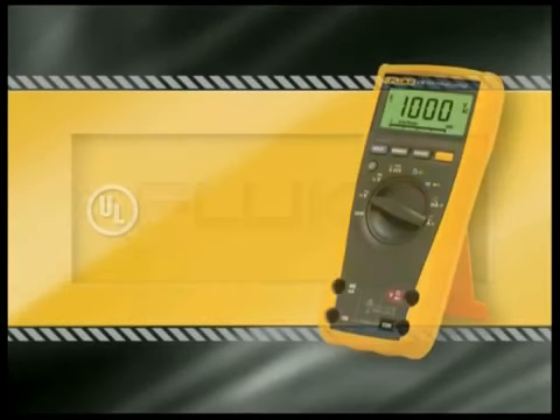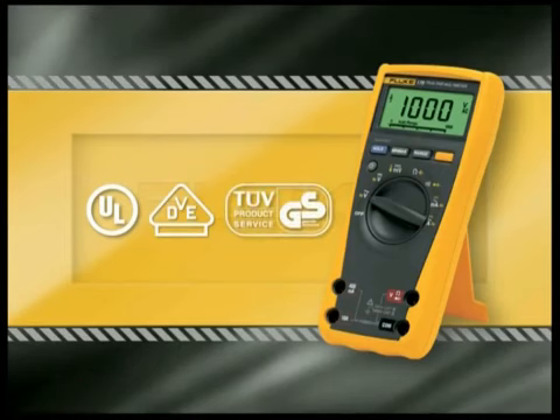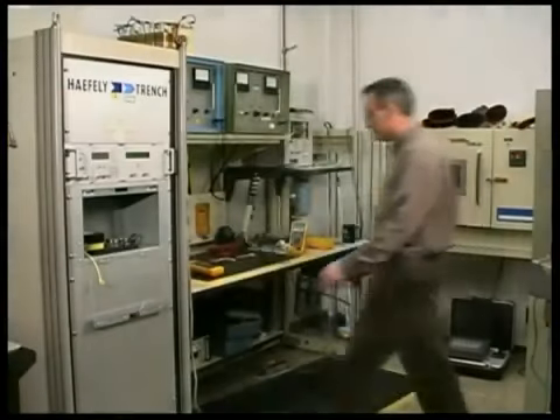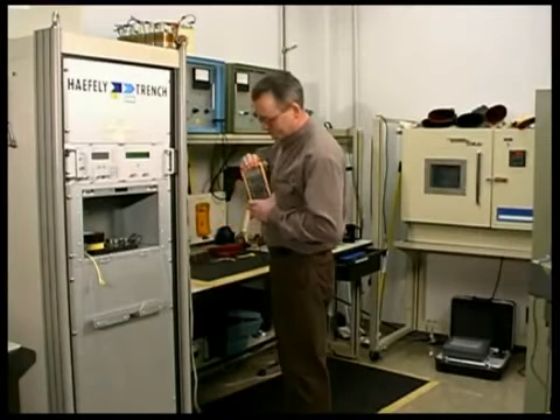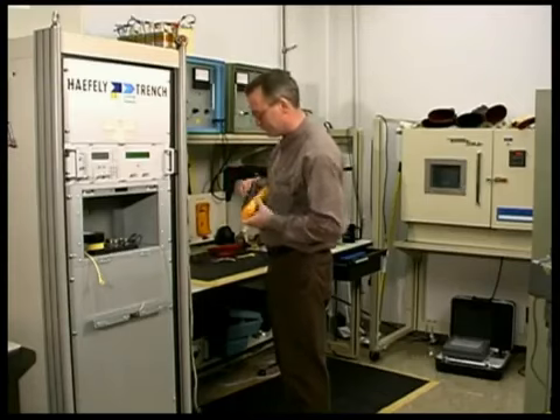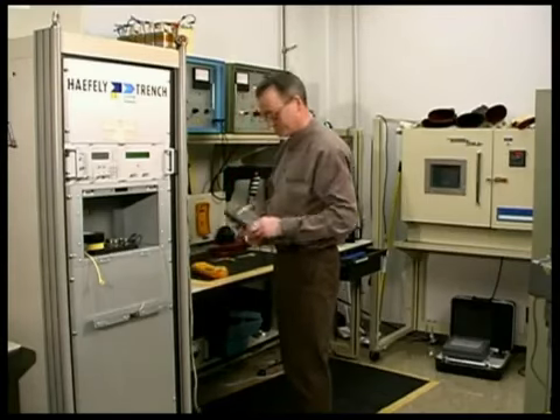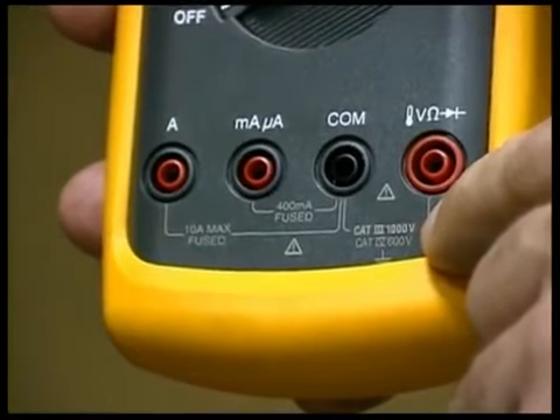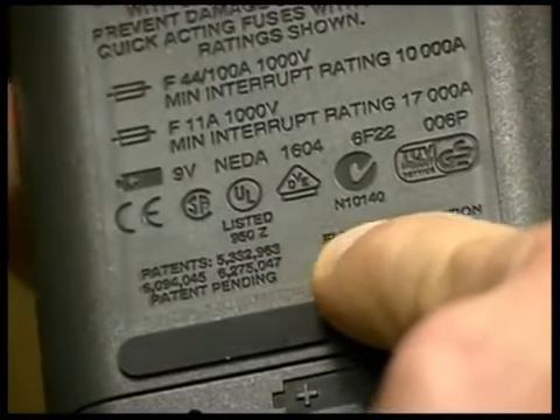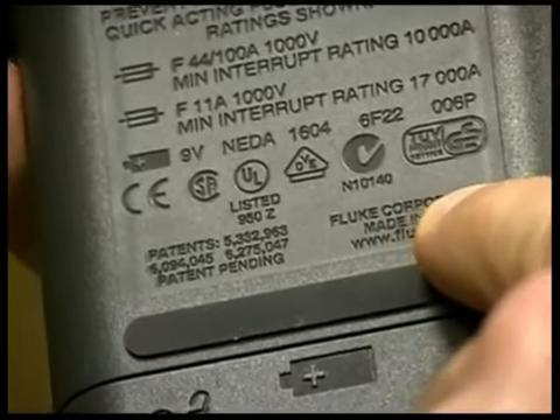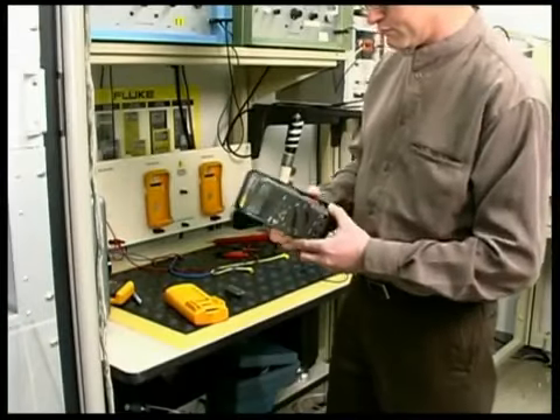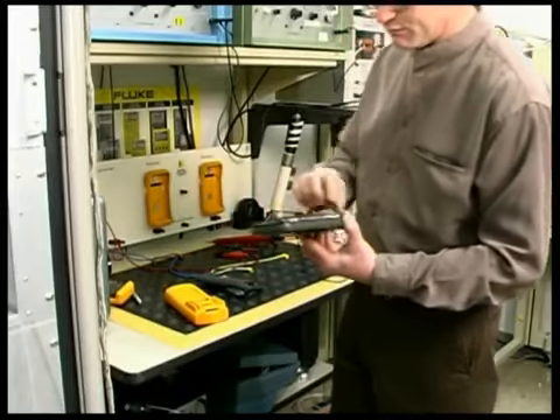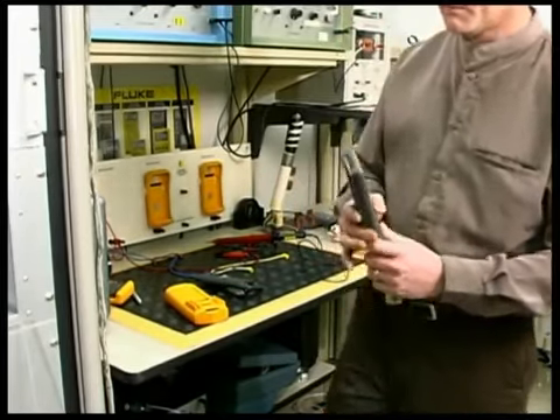Meters and other electrical test tools should be independently evaluated to make sure they can survive high-voltage transients. A special test machine is used to generate the overvoltage transient and fault current as defined by international standards. This meter is marked 1000 volts Cat 3 on the front of the case and has been certified by an independent testing laboratory. A 1000-volt Category 3 tester is required to survive a minimum of 10 transients of both positive and negative 8000 volts without creating a hazard.